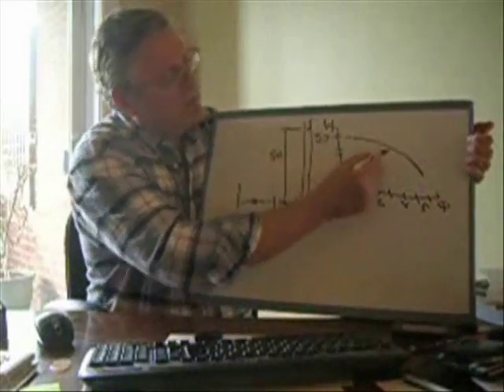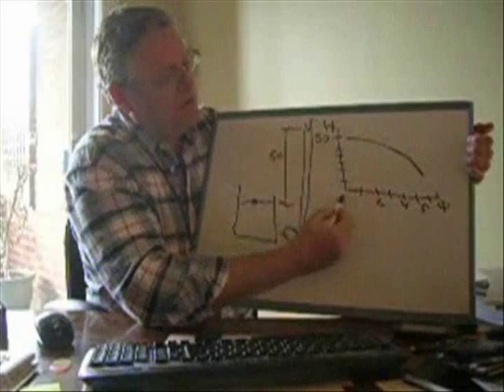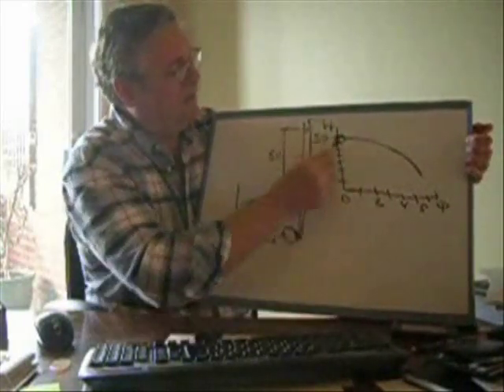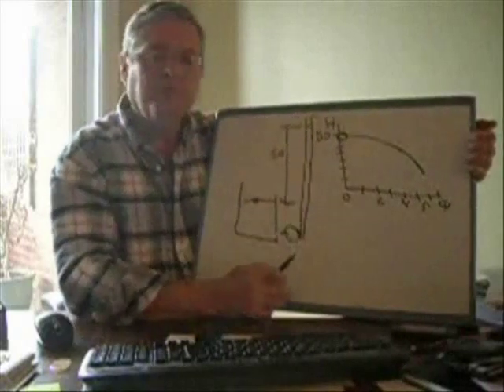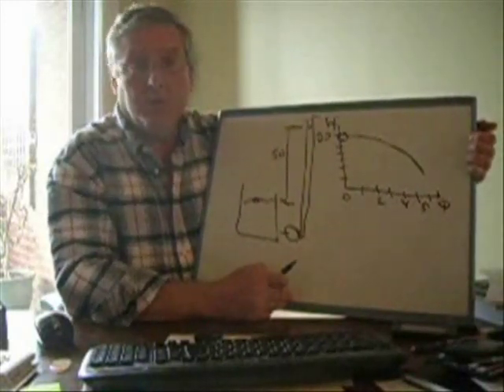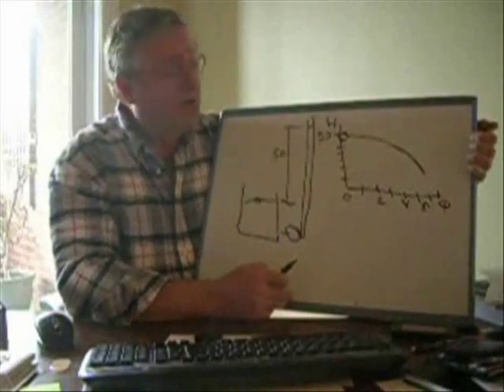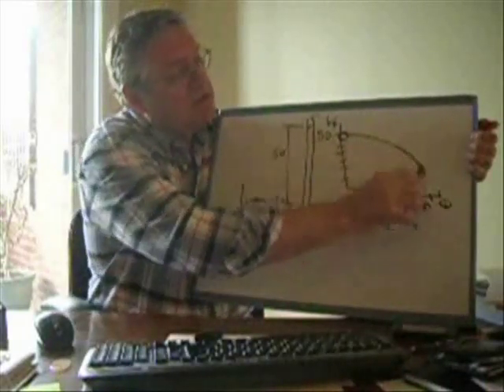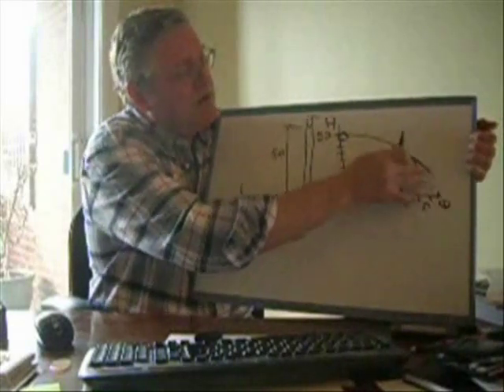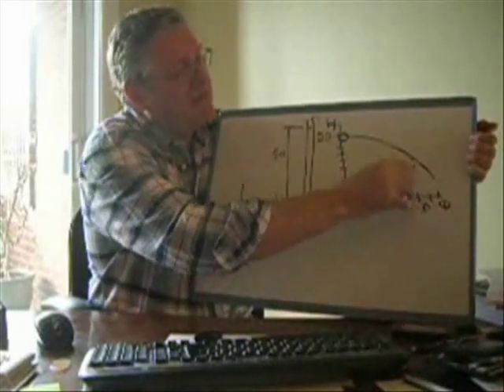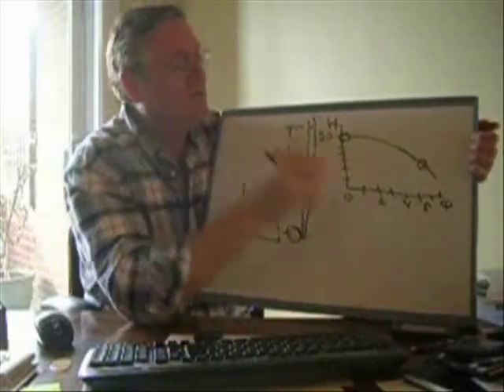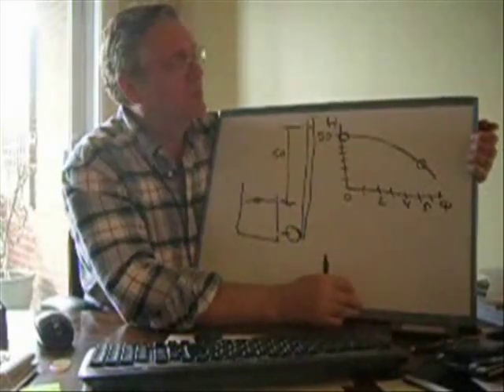So let's say 50 to match up with what I was saying here. So the pump is operating on this curve when it gets to zero flow. This is zero right here. We're going to be at this point. And that's 50 feet. So this is how high this pump is going to be able to pump at zero flow. Of course, normally we want flow and we're not at zero flow. So the pump is going to be operating somewhere else on this curve. In our case, we want to see something like 5, 7, whatever. So this is 7 here. We would be somewhere around there. That's what we're looking for in terms of a pump.